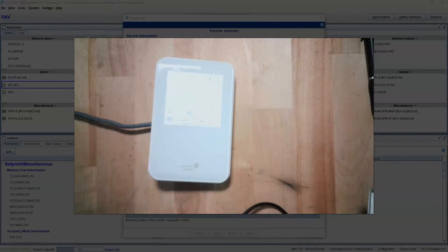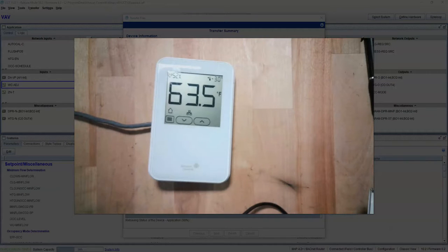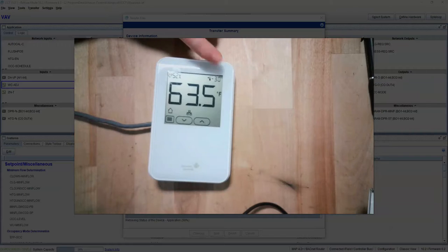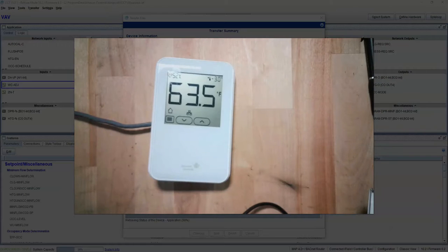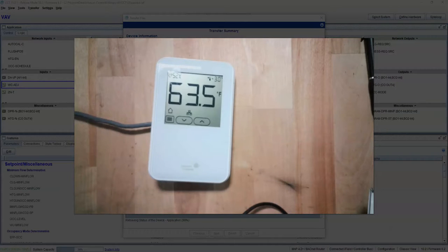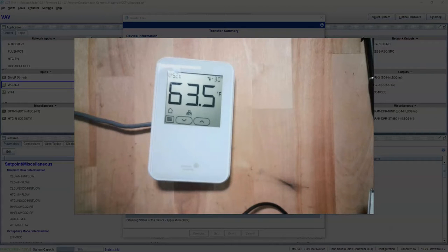Other than that, the stat looks the same. But now we got warm cool adjust. As you notice in the upper corner there, we don't have the actual setpoint, but we have what's relative to the setpoint where we're minus three degrees from the setpoint. Right now we don't know what that setpoint is, but we are minus three degrees.